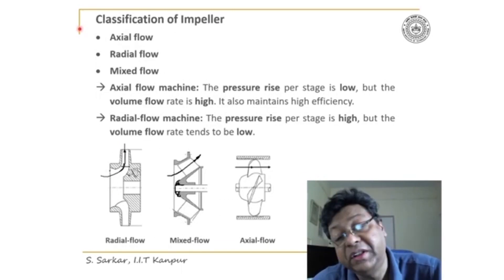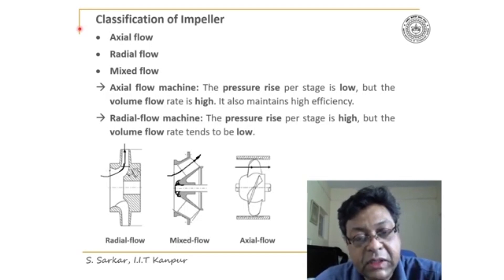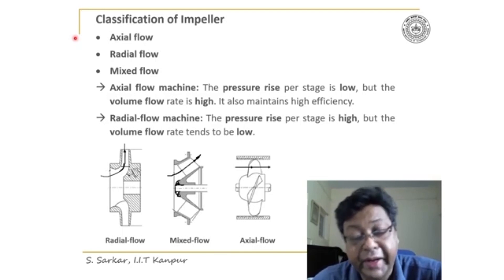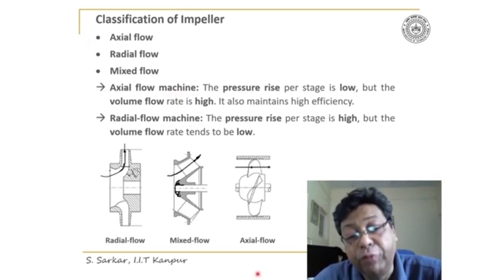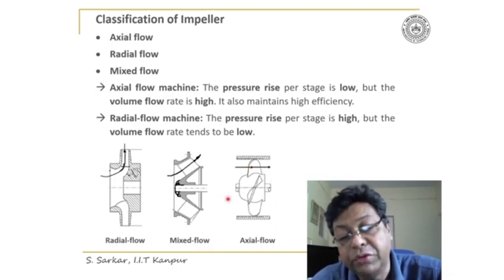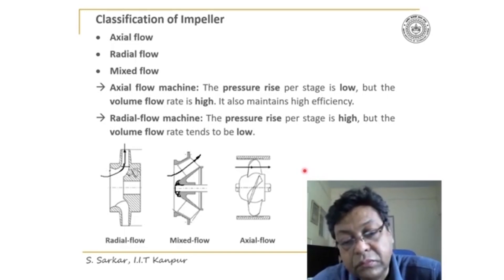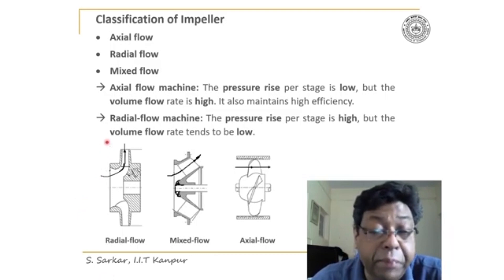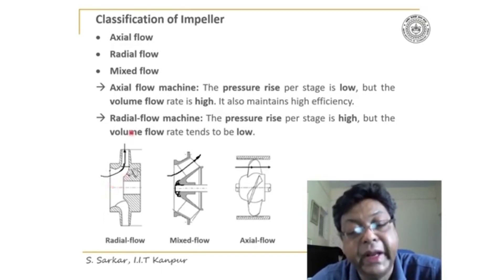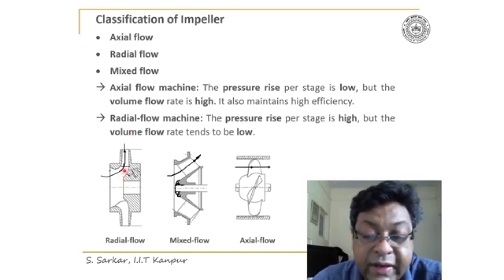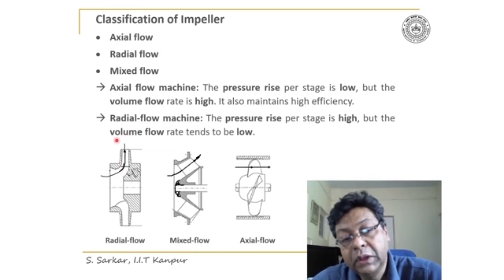The impeller can be classified further based on the direction of flow as it passes through the impeller: axial flow impeller, radial flow impeller, and mixed flow impeller. In an axial flow impeller, the flow enters parallel to the axis of rotation and also leaves the impeller axially. In a radial flow impeller, the flow enters parallel to the axis of rotation but then turns in the radial direction — when it enters the blade it becomes radial, and it leaves in the radial direction.